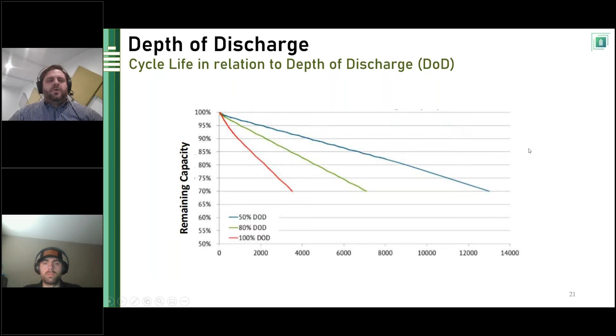So occasional discharges down to 100% are fine, but just as a matter of warranty and also as a matter of customer satisfaction, because all these customers want their batteries to last a long time, going down to 80% on a day-to-day basis is the way to go, regardless of whether or not the battery says on the data sheet only use 80% or only use 100%. I know one of our competitors says you get unlimited partial cycles, to kind of imply that, hey, these batteries are going to be outlasting the 10-year warranty on their data sheets. So how you use the battery will govern how long the battery lasts beyond that. So long story short, while the batteries can do rapid discharging and deep discharging, staying within normal operating parameters is appropriate for longevity.